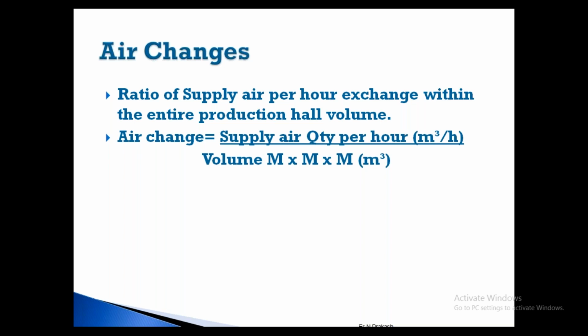So what is air changes? Supply air quantity per hour, in cubic meters per hour, divided by volume. Volume is the length, breadth, and height of your production hall. There will be a false ceiling. Below the false ceiling to floor level, what is the height? What is the width of the department? What is the length of the department? That constitutes the volume. So supply air quantity divided by volume, you will get air changes.